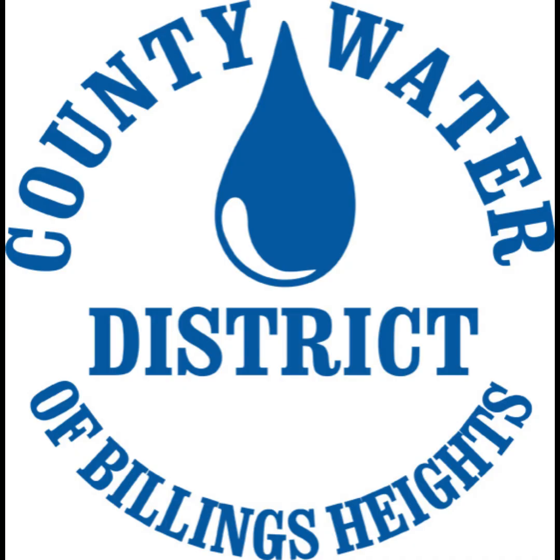I can speak to the reservoir elevations because we operate them there. They're very close, they're within a few feet of water surface elevation, which just basically means if the reservoirs are full, then they're going to be virtually the same pressure, especially as long as Oxbow has to go to get to the City of Billings connection. If you were to have, say, Oxbow completely empty or low on the low end, let's say it's 20 feet down, and we're at the high end, arguably you could have maybe a 50-foot difference there. And so you would want something to make sure that it's controlled.